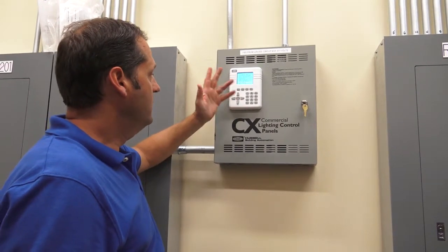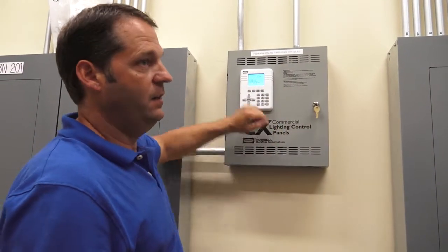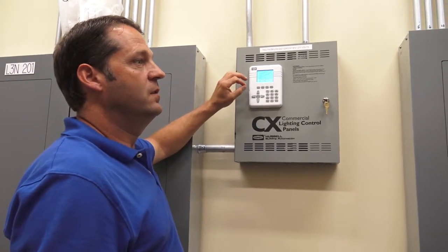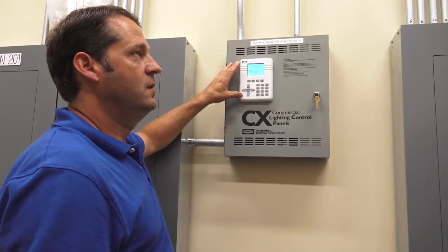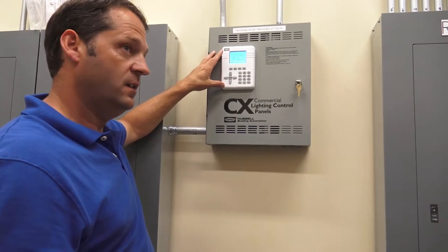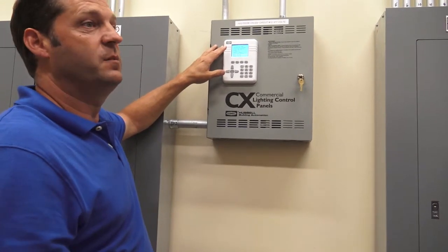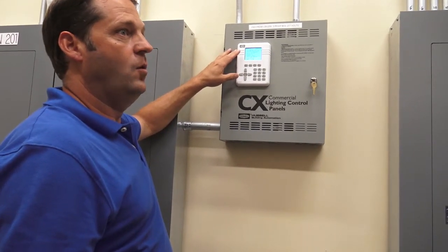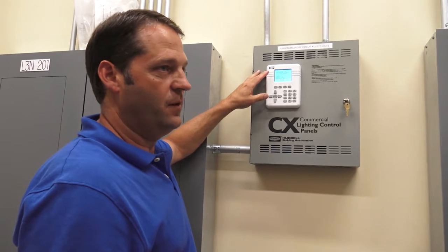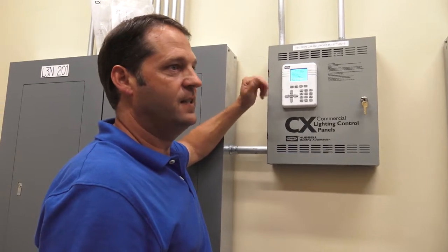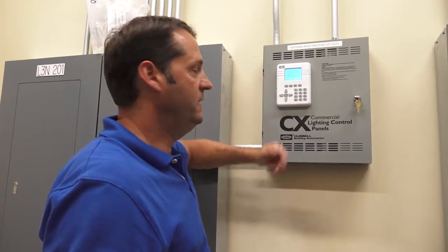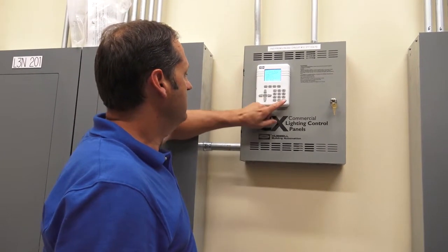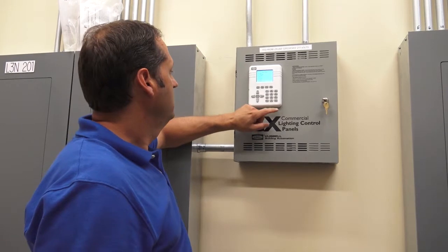Relay version, again, the relays that are in this panel. It would be less important with the switching relays than the dimming relays. Maybe you're having some dimming issues and it's an older dimmer that doesn't dim LEDs very well. You look at that and say, oh, you've got an old dimmer, you're trying to dim LEDs, you need to fix that. A reboot system is exactly what it says, it reboots the system. Okay.